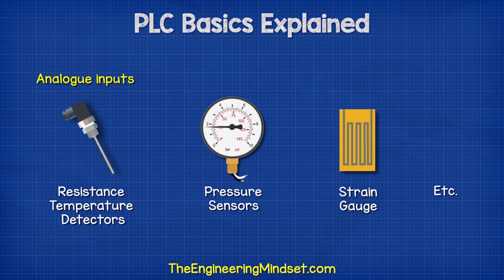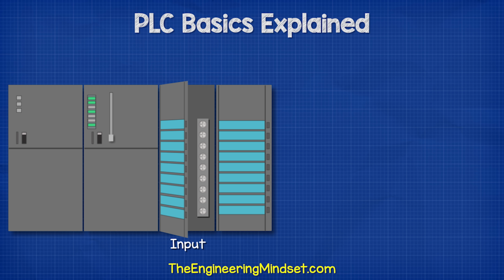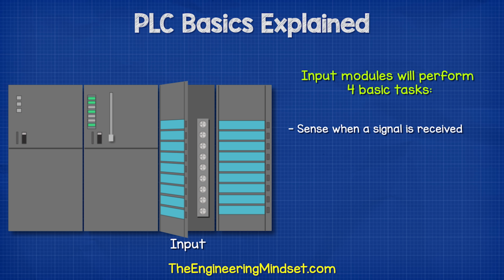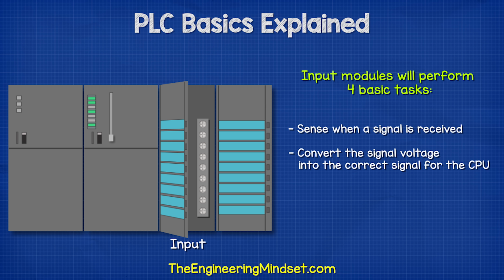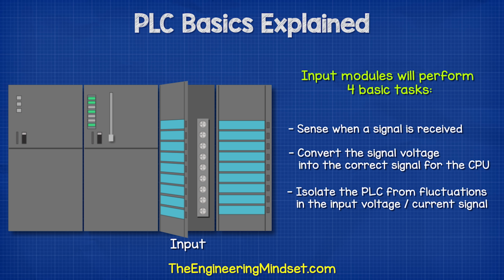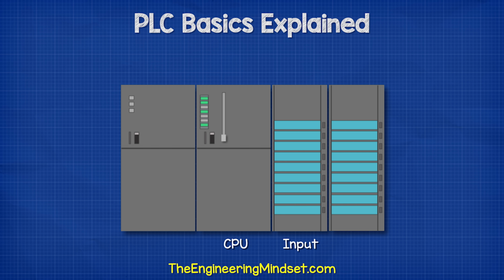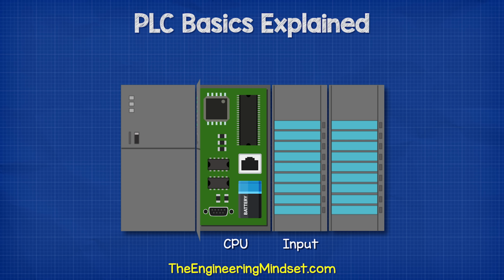We will look at that a little later in this video. Input modules will perform 4 main tasks. They sense when a signal is received, they convert the signal voltage into the correct signal for the CPU, they isolate the PLC from fluctuations in the input voltage or current signal, and they send the corrected signal to the CPU.